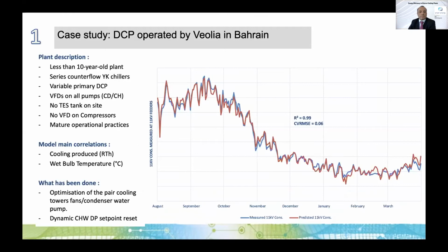The first case study has been done on a plant that we've talked a lot about today, which is the plant where I started my career, actually, in Veolia in Bahrain. This is a relatively modern plant. It's less than 10 years old. It's got a series counterflow YK chillers arrangement, and it's got just variable primary pumping. There's no TES. There's no secondary pumps. The great thing is that it's got VFDs on both condenser and chilled water pumps, but not on the compressors.